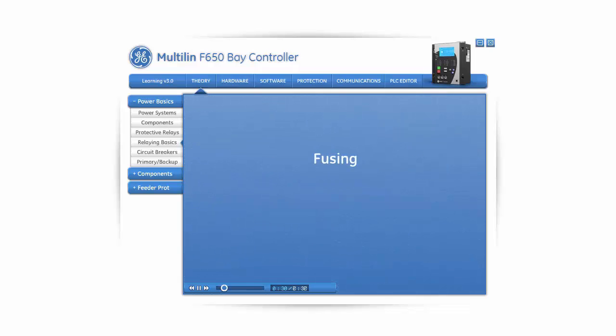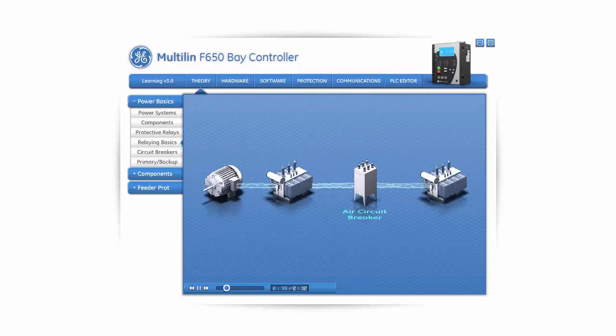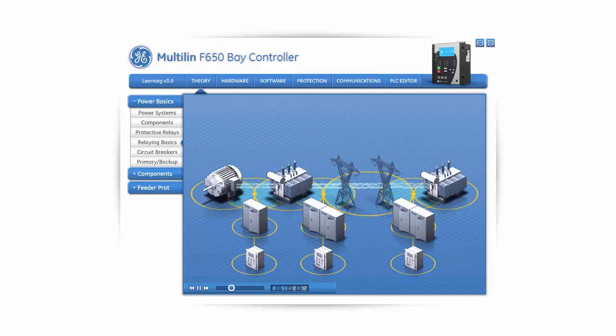Fusing, reclosers, and sectionalizers are employed in some cases to keep costs down. Circuit breakers are located between each power system component, which makes it possible to isolate and disconnect the faulty component. If a breaker isn't installed between two adjacent components, both components will need to be disconnected for a failure in either one. One of the protection engineer's most powerful tools is the concept of zones of protection.